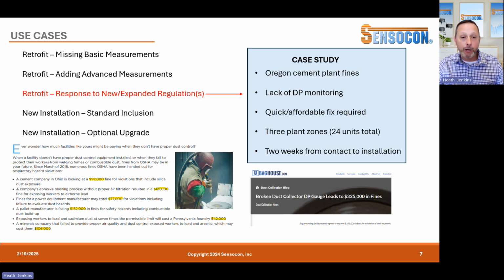Basically, a $50-$60 differential pressure gauge resulted in $325,000 in fines. There's some fine print there - I'm sure they would have been fined for the gauge regardless, but they had also falsified records, which I think hurt them more than anything. It's a nice highlight of the risk businesses face if dust collection parameters aren't monitored correctly and kept up to date with state and local regulations.